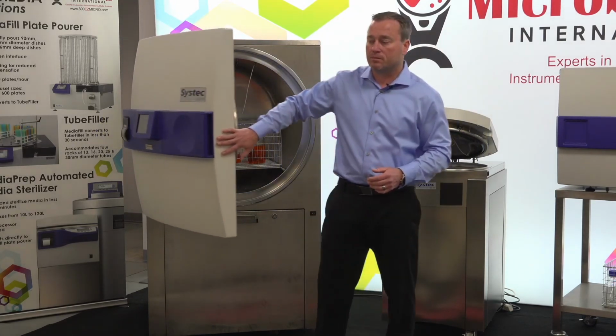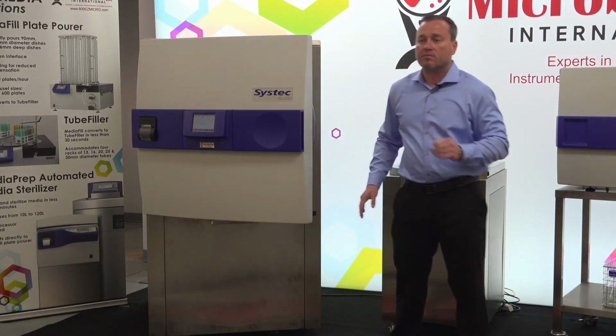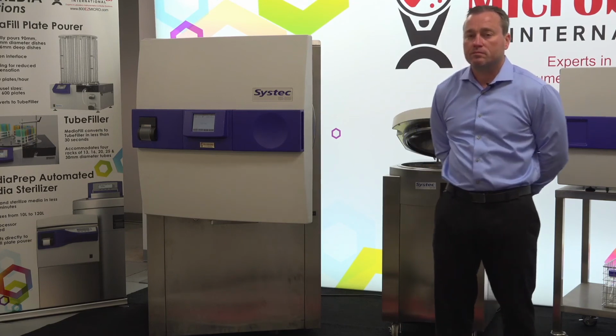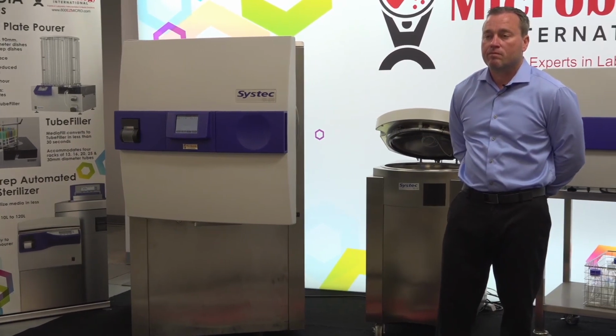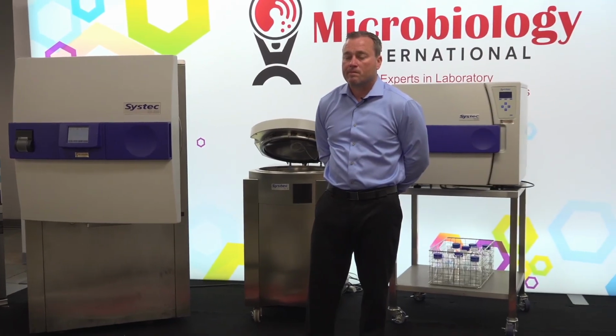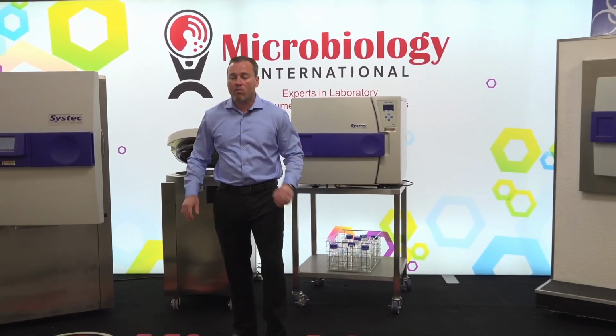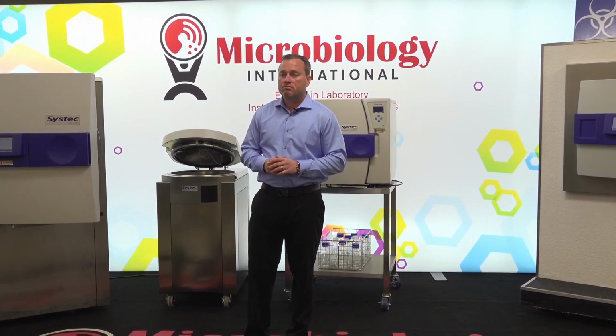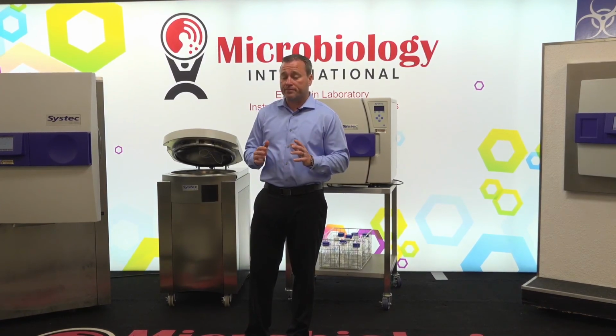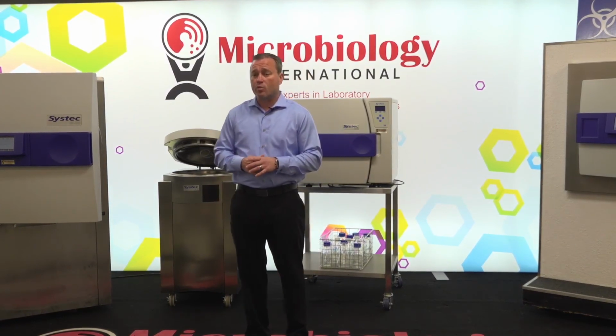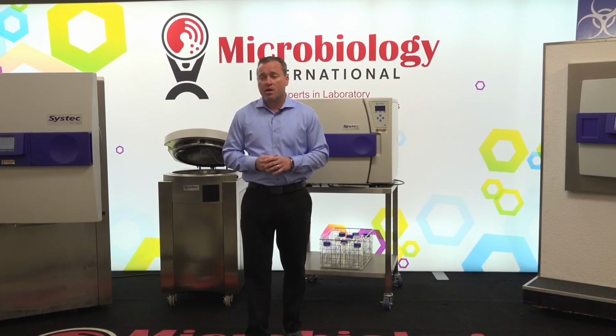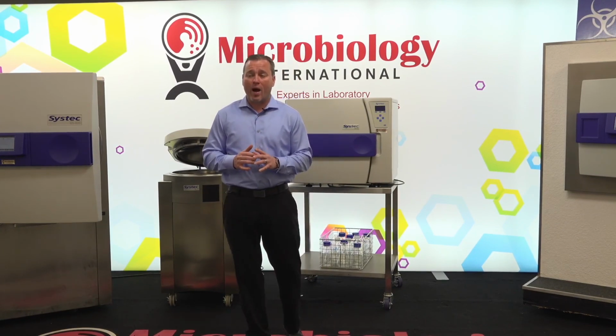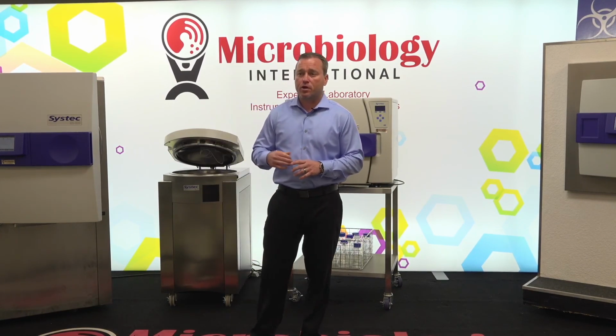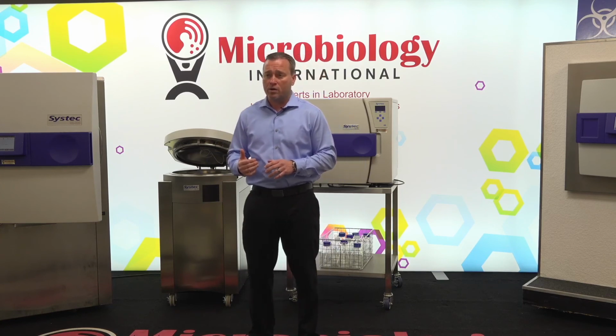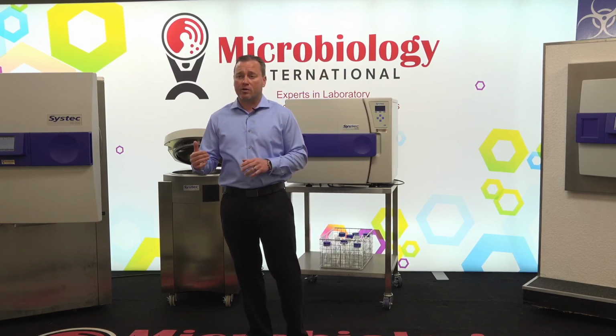All right, looks like we got another one. Aside from the media and the water that you spoke about for liquids, sterilizing liquids in the chambers, are you able to sterilize other liquids such as milk? Yes, we've just recently done this, so we do offer pasteurization cycles. The way that works, though, is quite a bit different than just sterilization, because we don't want to achieve 121. We probably only want to go to 90 degrees C or something like that for a briefer period of time.